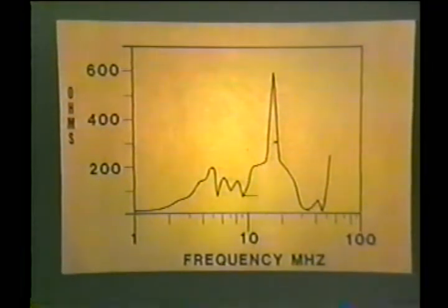Likewise, on another machine at a higher frequency range, this time between 1 megahertz and 50 megahertz, you can see a cluster of frequencies at 2, 3, 4, 5, 6, 7, 8, and 9 megahertz, and a very sharp increase in impedance at 17 megahertz. In particular, those between 4 and 9 megahertz were also characteristic of standing waves.